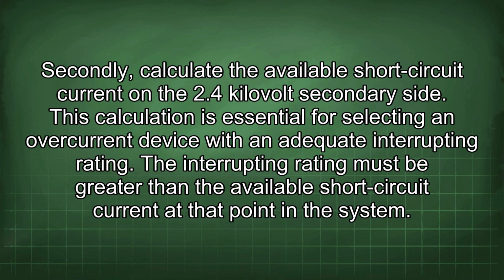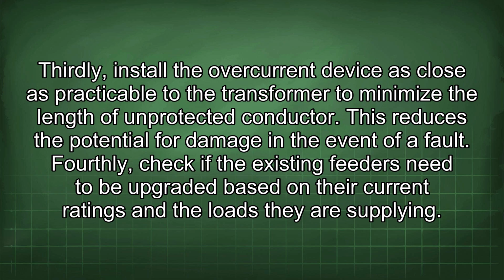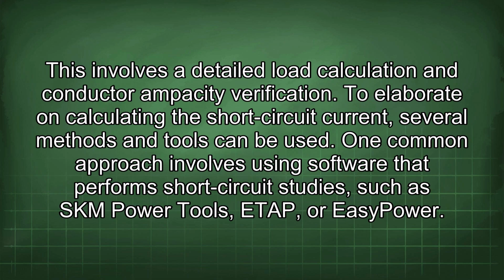Secondly, calculate the available short-circuit current on the 2.4 kV secondary side. This calculation is essential for selecting an overcurrent device with an adequate interrupting rating. The interrupting rating must be greater than the available short-circuit current at that point in the system. Thirdly, install the overcurrent device as close as practicable to the transformer to minimize the length of unprotected conductor. This reduces the potential for damage in the event of a fault. Fourthly, check if the existing feeders need to be upgraded based on the current ratings and the loads they're supplying. This involves a detailed load calculation and conductor ampacity verification.